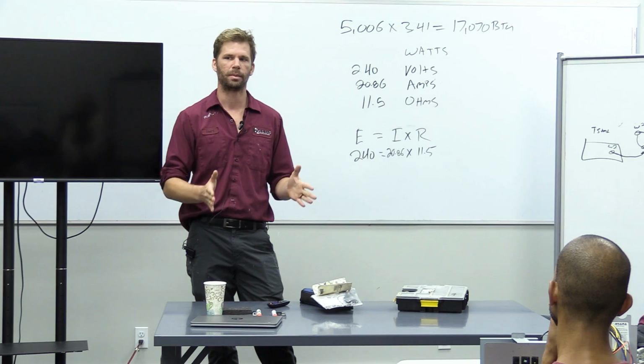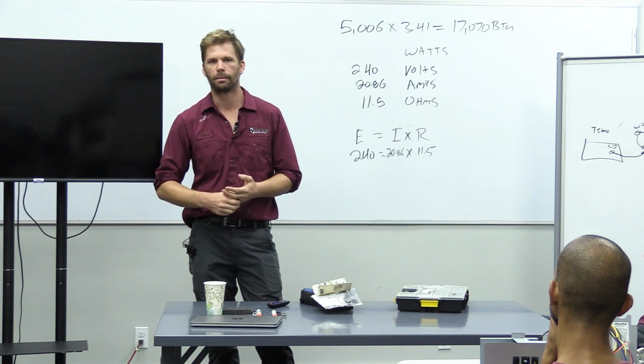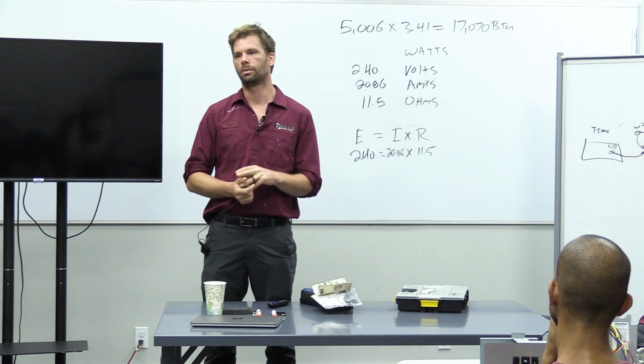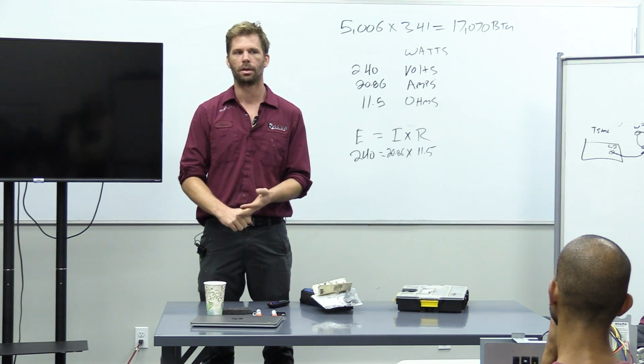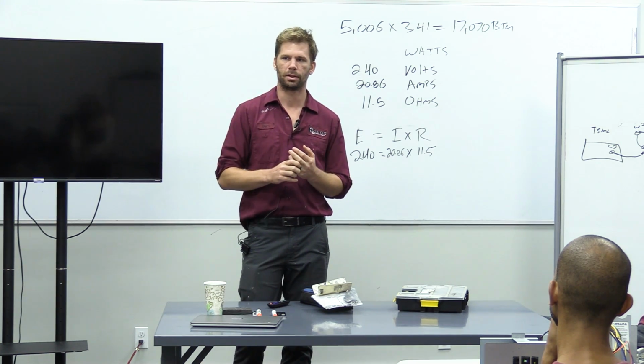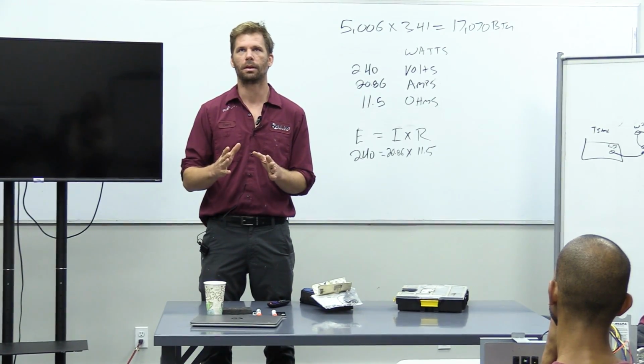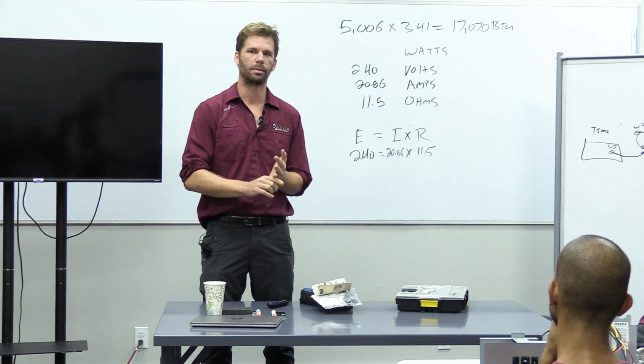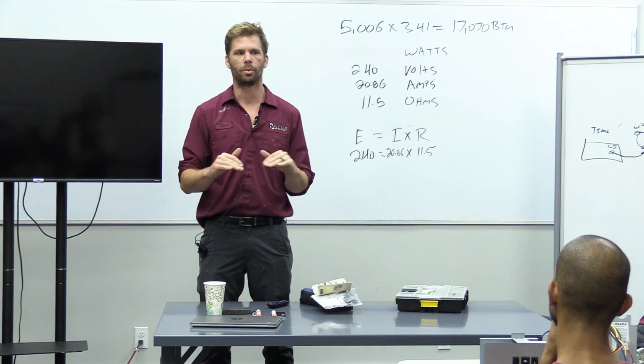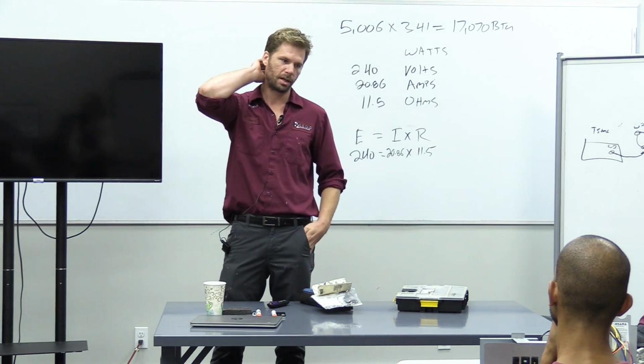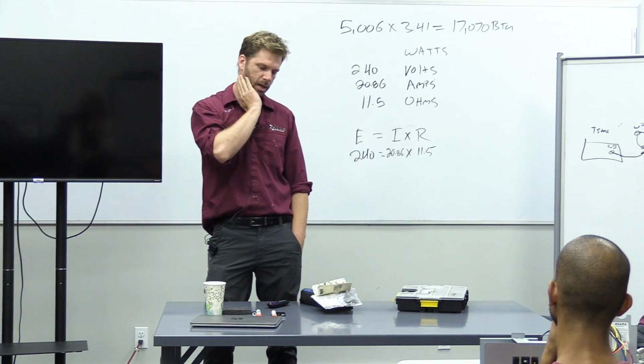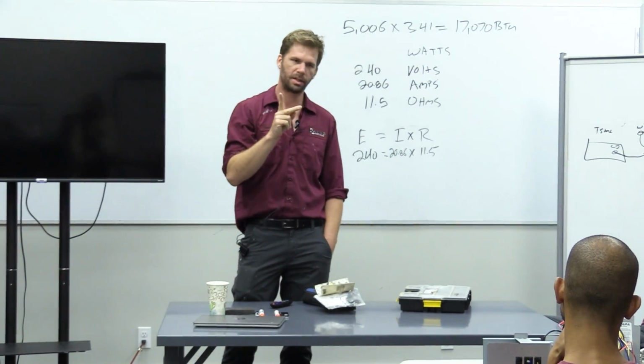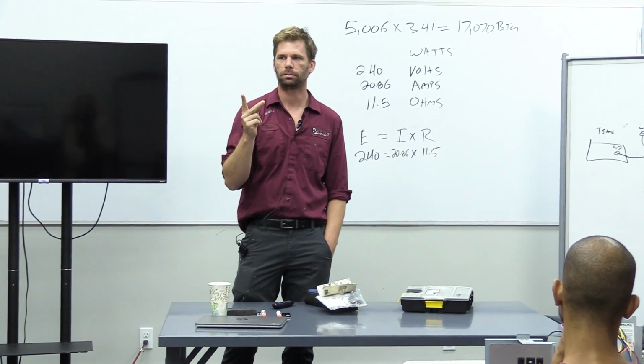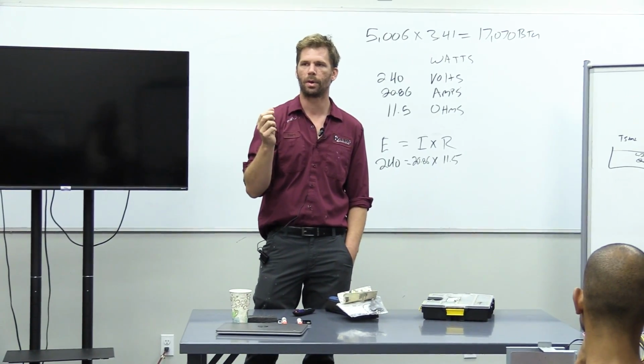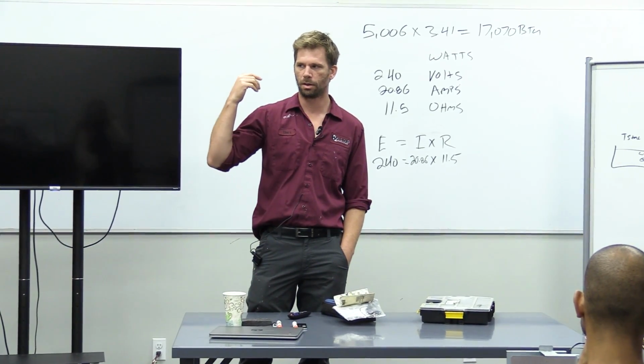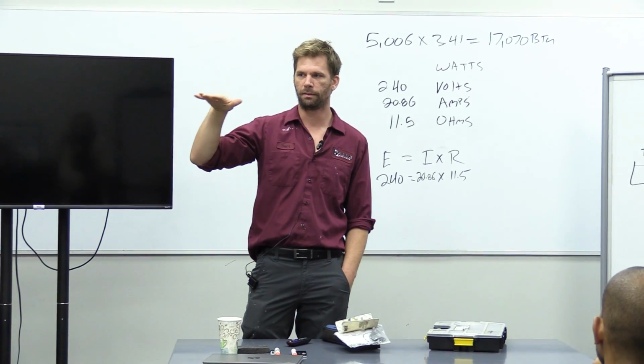So we actually have the correct amount of charge for this pool heater. And so, same situation, you're gonna run into a lot of extreme temperatures where your water temperature is really low, outdoor temperature is really low. You're gonna have very low pressures. You can't just show up and start adding refrigerant. Get familiar with the concept that low water temperature, low outdoor temperature, you're gonna see really extreme low pressure. And that's why they all have some sort of defrost mechanism in them. So a heater is gonna have typically 2 thermostats, one for water, one for defrost, connected to the board. And it's gonna have, on the defrost, the only function is it shuts your fan off. Shuts your compressor off and just leaves the fan on.